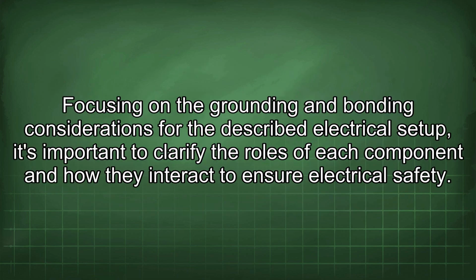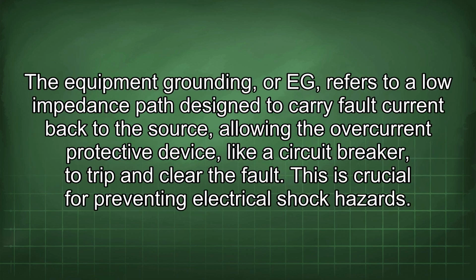Focusing on the grounding and bonding considerations for the described electrical setup, it's important to clarify the roles of each component and how they interact to ensure electrical safety. The equipment grounding, or EG, refers to a low impedance path designed to carry fault current back to the source, allowing the overcurrent protective device, like a circuit breaker, to trip and clear the fault. This is crucial for preventing electrical shock hazards.